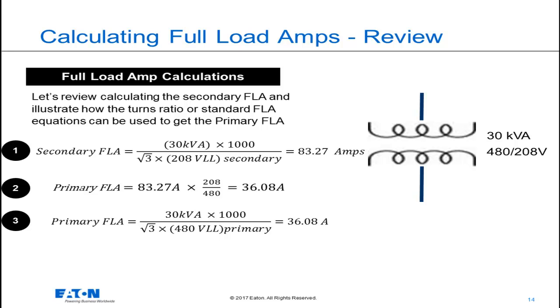One, I'm going to leverage the turns ratio of the transformer, and I do that in equation number 2. To calculate the primary full load amps by using the turns ratio, I take the secondary full load amps, and I multiply that by 208, the secondary voltage, and divide it by the primary voltage, which is 480 volts. And I arrive at 36.08 amps.